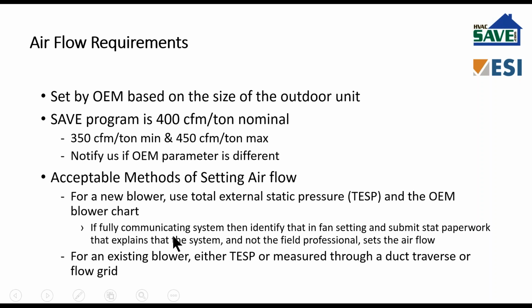Now we are seeing more and more of these fully communicating systems in which our understanding is that in most cases the field professional does not set the airflow, rather the system sets the airflow. If that is the case, you need to identify that in the fan speed setting and you need to submit that paperwork or that logic, that language, the utility that explains just that the system and not the professional sets the airflow. Perfectly acceptable. Utility just needs to verify.